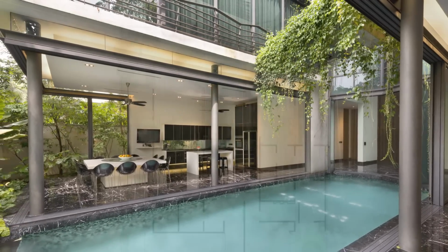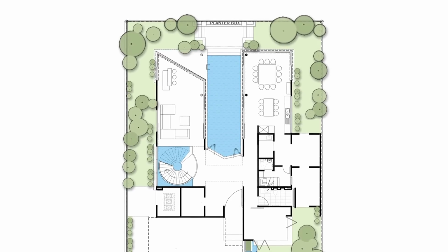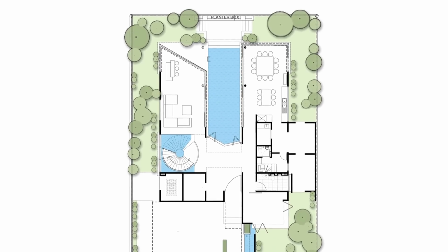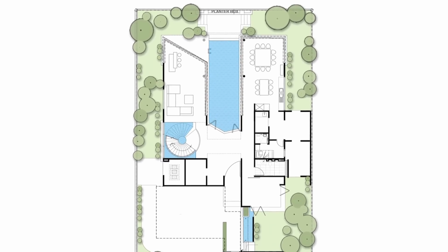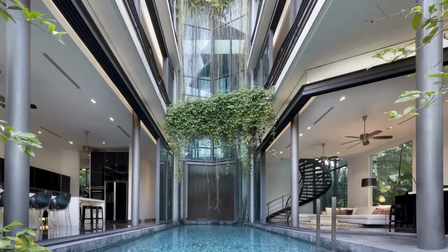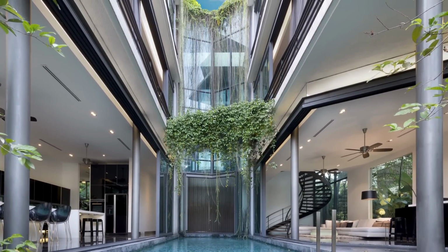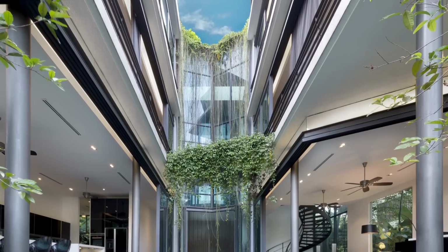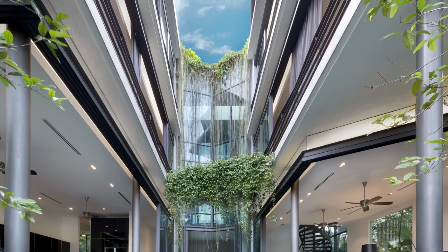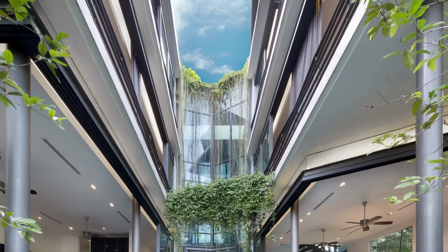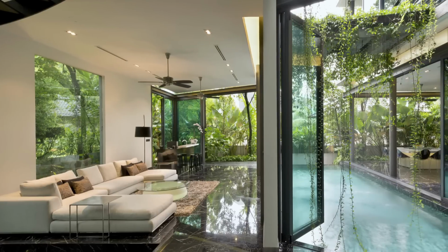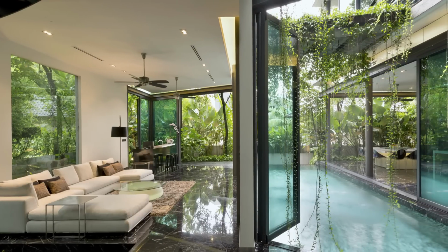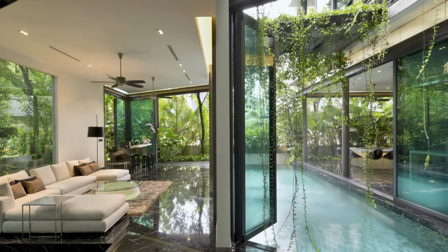The two wings of the house form a U shape around the pool, which helps create an upward draft of air above the pool. With all the main living areas able to be opened up to the pool, this draft sets up a natural air circulation and pulls air out of the interior. The U shape also maximises the perimeter walls and reduces the building's depth, so increasing the cross-ventilation effect.